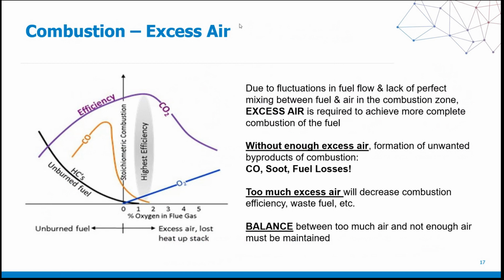We're creating the carbon monoxide that I just went over, the soot, and we're having fuel losses or appliance inefficiencies. With too much excess air, we're decreasing the combustion efficiency, we are wasting fuel, creating pulling of the flame, and things like that. So the goal with all of this is to strike a balance between too much air and not enough air, and it must be maintained. So the perfect fuel to air ratio that a combustion analysis can assist you in getting towards is what we're looking to go for.